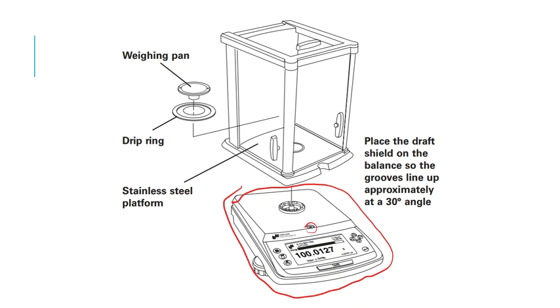There's always a level bubble on top that I check to make sure these things are in fact level. If not, they have adjustable feet I can screw to make them higher or lower to get that balance pan level, because level is key. Always double check that bubble and make sure it's in the middle of where it needs to be. If not, we need to level it, since balances can get moved throughout the day or week.